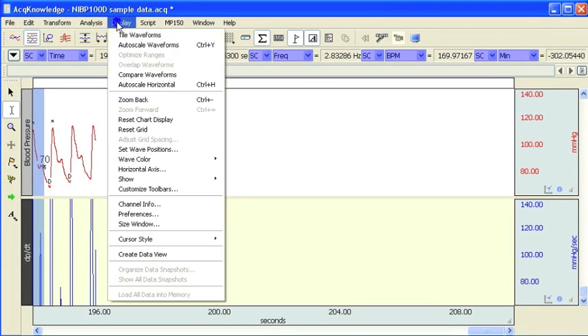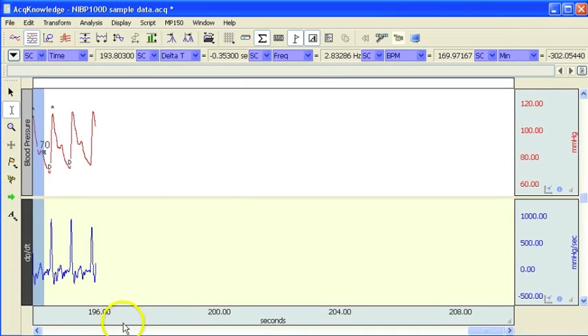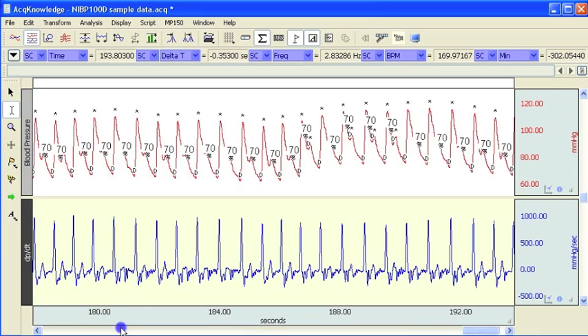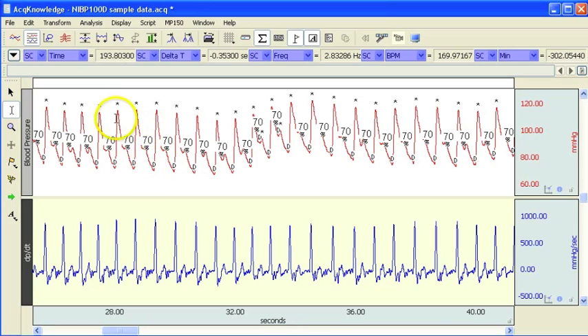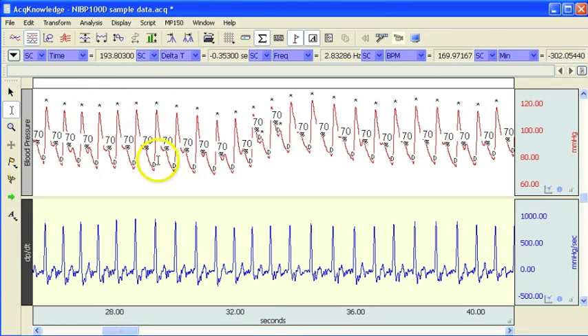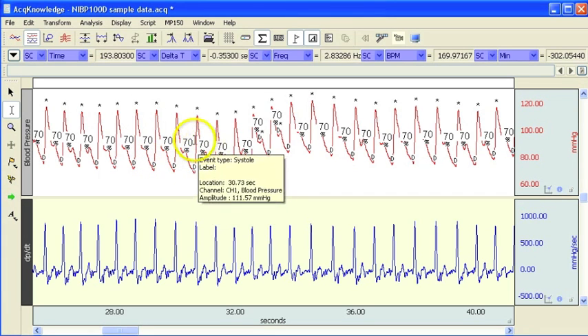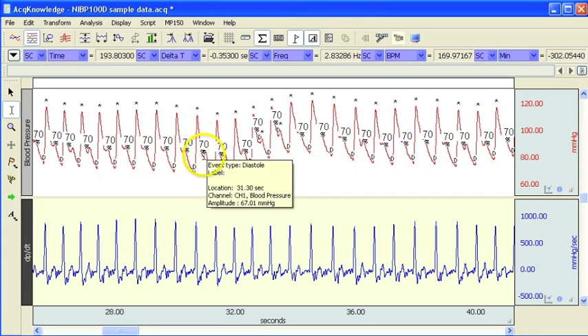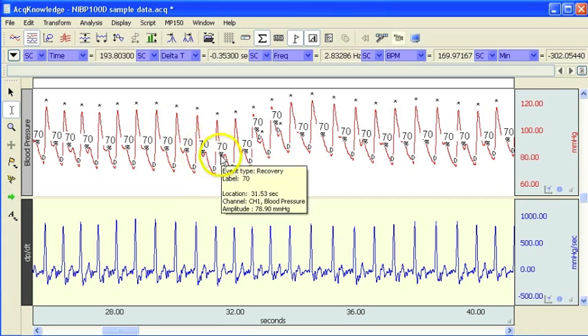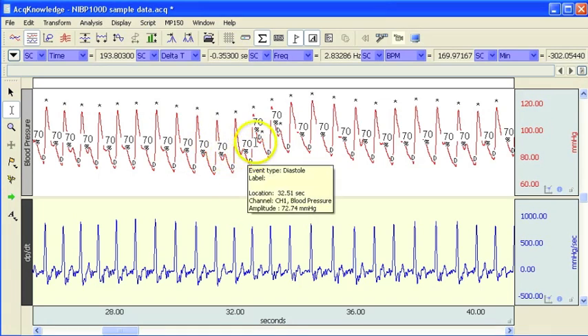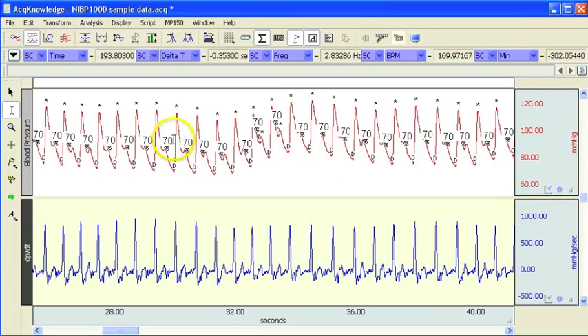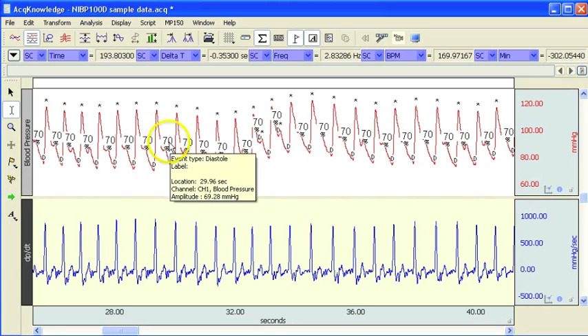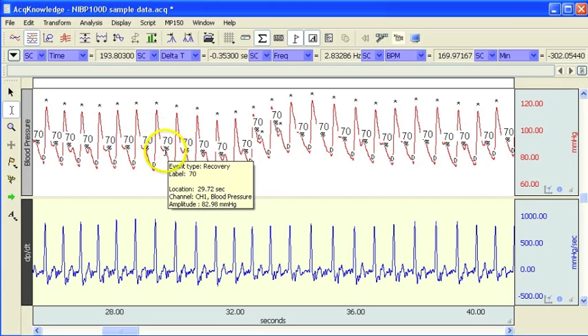If I auto scale and then come back through, we can see up above on the arterial waveform, the software has marked the systolic point with the asterisk and the diastolic with a D. And then we put in a 70% recovery that has also been marked on the waveform. And obviously if you want to mark different recovery points, you can do that by just changing the value from 70 to whatever number you're interested in.